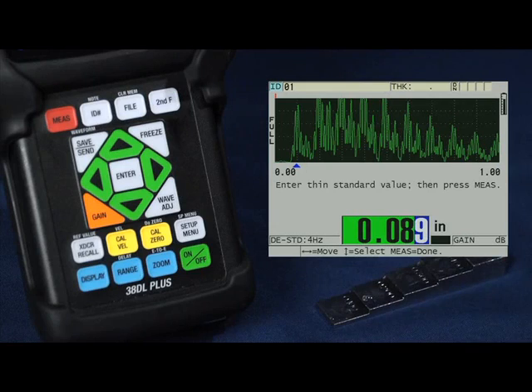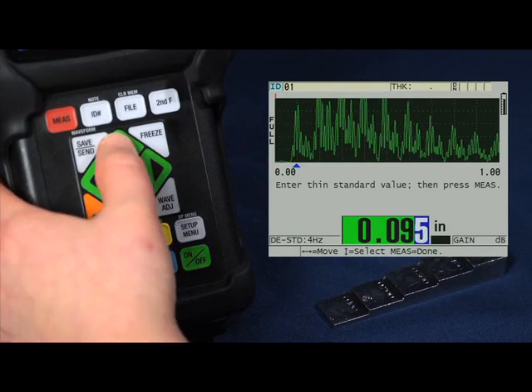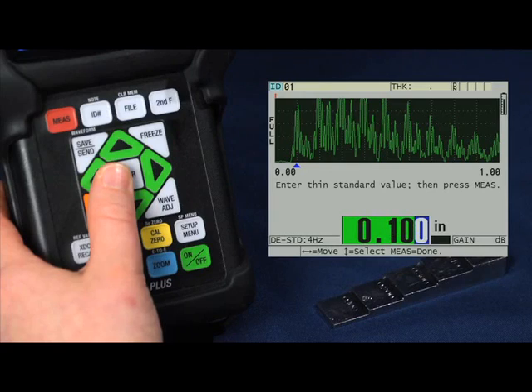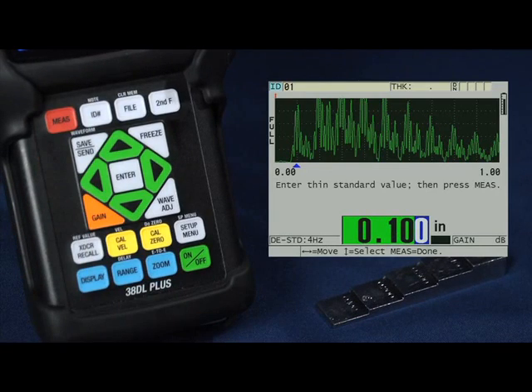Now again, you can use the up, down, left or right keys to enter in the known value of the thickness standard. Then press the red measure key to complete your calibration.